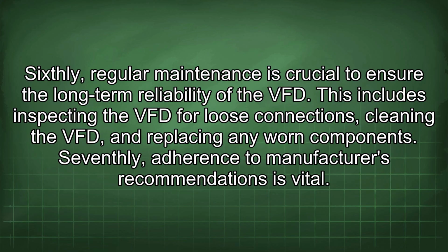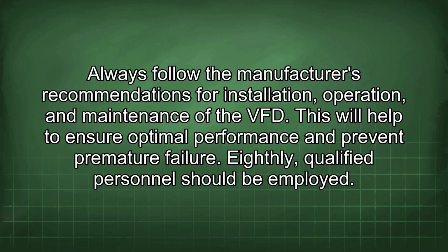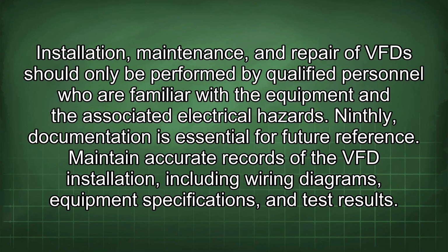Sixthly, regular maintenance is crucial to ensure the long-term reliability of the VFD. This includes inspecting the VFD for loose connections, cleaning the VFD, and replacing any worn components. Seventhly, adherence to manufacturer's recommendations is vital. Always follow the manufacturer's recommendations for installation, operation, and maintenance of the VFD. This will help to ensure optimal performance and prevent premature failure. Eighthly, qualified personnel should be employed. Installation, maintenance, and repair of VFDs should only be performed by qualified personnel who are familiar with the equipment and the associated electrical hazards.